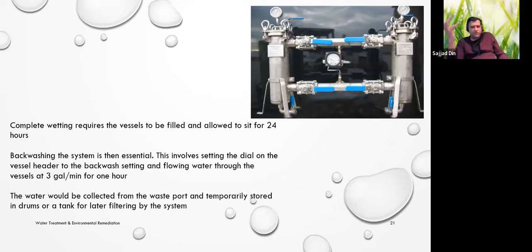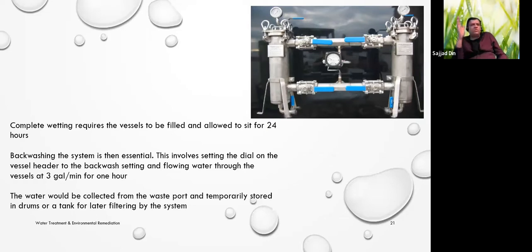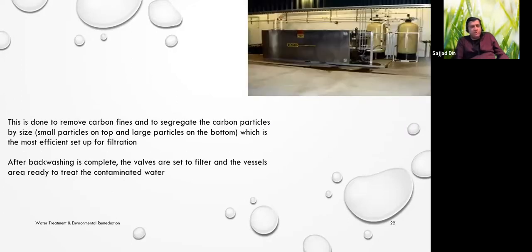When we start up a system, we check for leaks and let it wet for 24 hours. You can't simply turn on the system and assume it will work properly. Maybe your goal is to pump at 200 gallons per minute, but you start off at 3, 4, or 10 gallons per minute — slow rate, check, and see what's going on. One of my successful projects had us pumping at about 70 to 75 liters per minute, but we couldn't do that right from the start. Before pumping into the sewer, you also have to sample.